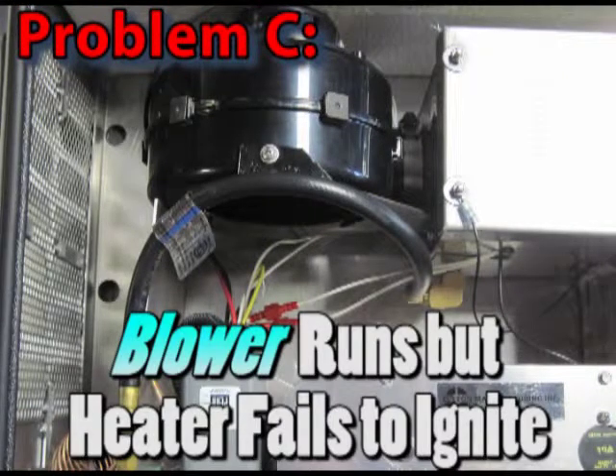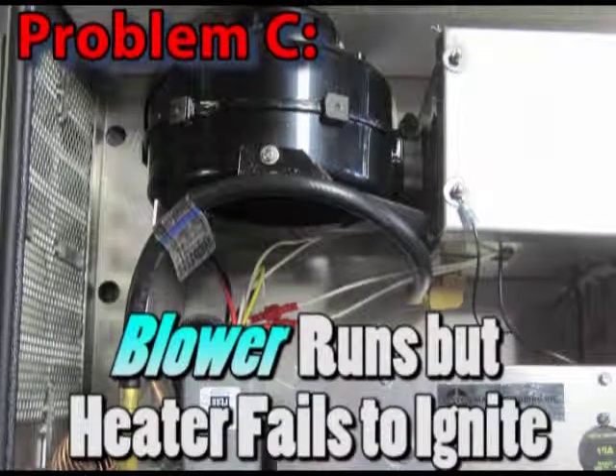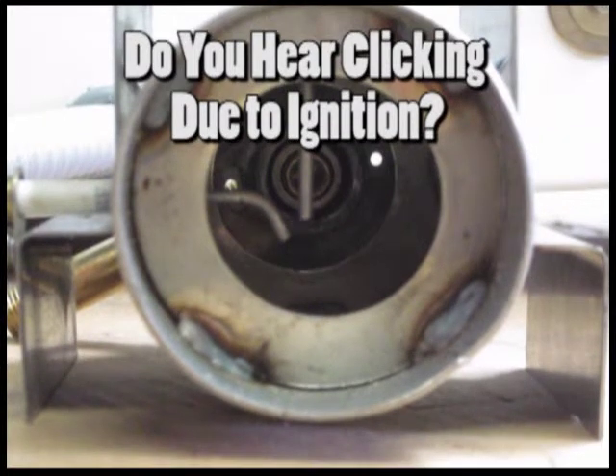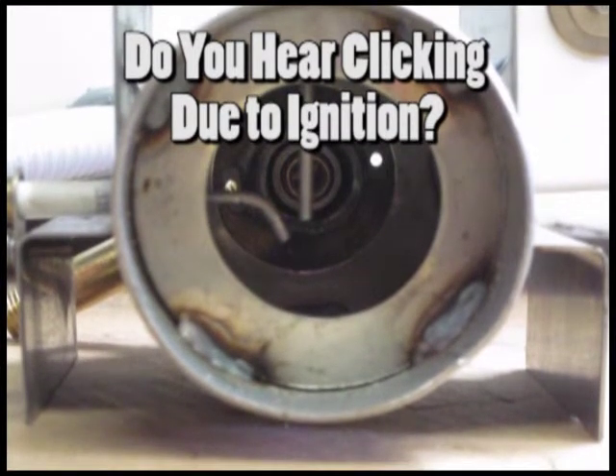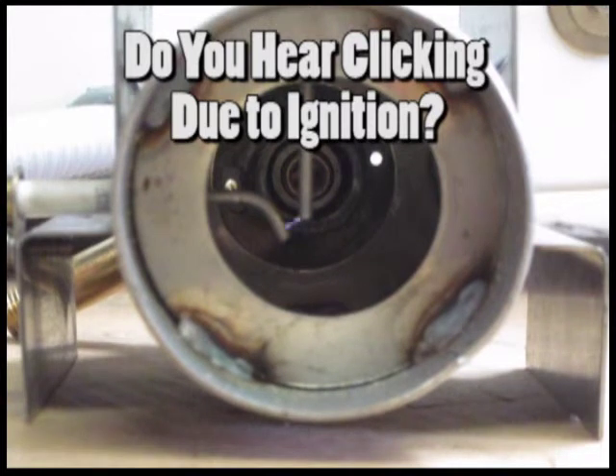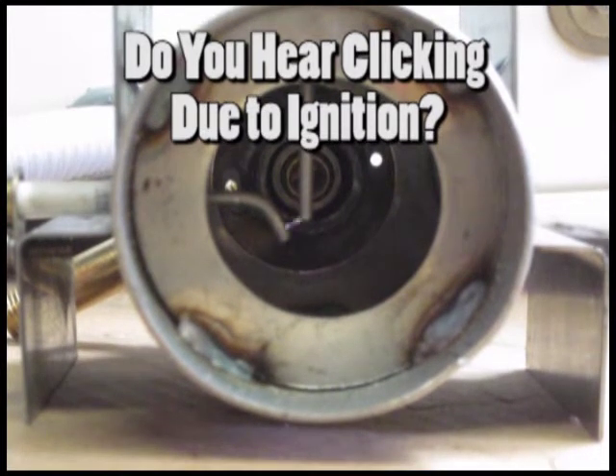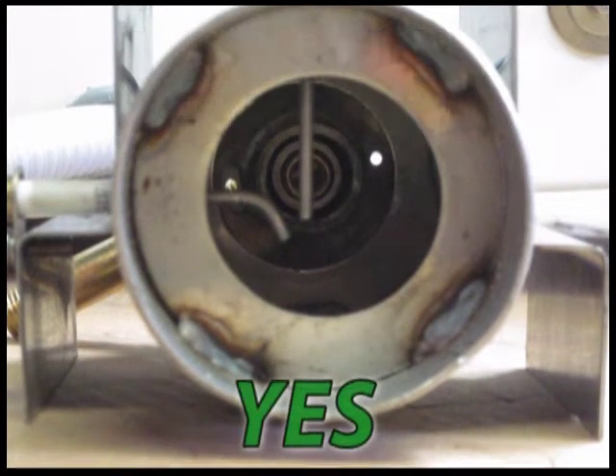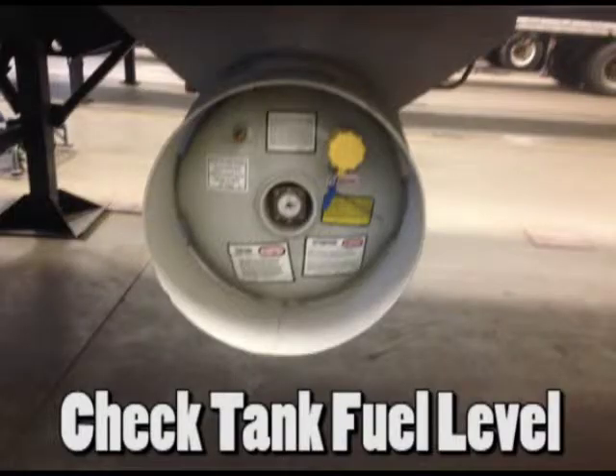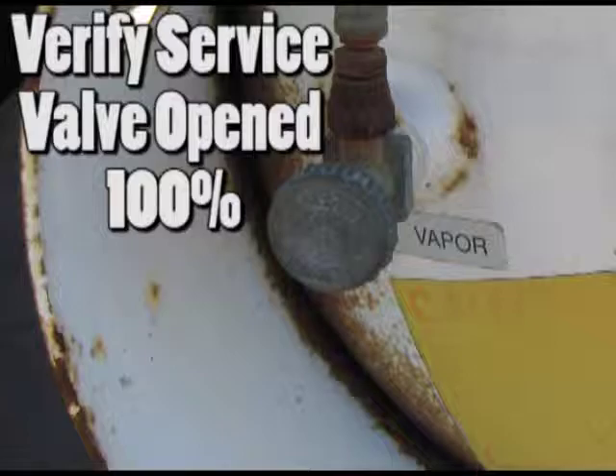Problem C. Blower runs but the heater fails to ignite. Do you hear 3 trials of clicking noises with 7 seconds between each trial, 15 to 30 seconds after you turn up the thermostat? This sound indicates the heater running through its ignition phase. If so, check the fuel system, especially that the propane tanks contain fuel and that the service valve on the tanks is open. Confirm that the heater is getting fuel.